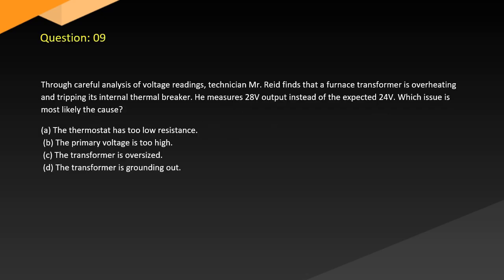Question 9. Through careful analysis of voltage readings, technician Reed finds that the furnace transformer is overheating and tripping its internal thermal breaker. He measures 28 volts AC output instead of the expected 24. Which issue is most likely the cause?